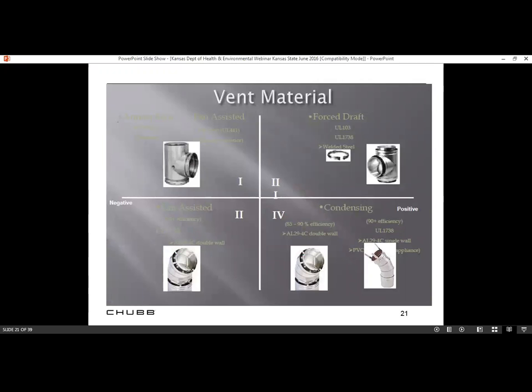Another area that a lot of people could probably save in efficiency and energy is their vent material. I've been in a lot of facilities where they just basically put up some exhaust ductwork and think that's going to make it. But in reality, there are standards out there, UL standards for vent material, that will actually benefit the customer and reduce their overall costs, so you don't have excess air and excess moisture in the stack.